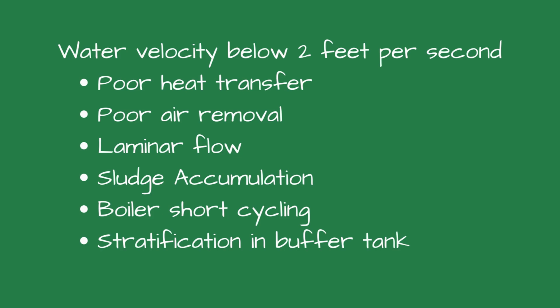At low velocities, small air bubbles tend to cling to the pipe walls instead of being swept along to the air separators. This leads to air pockets or air locking in terminal units, which reduces heating capacity and can cause gurgling noises. Poor air removal increases the risk of corrosion in the system. Flow may become laminar, smooth layered flow, rather than turbulent. Turbulent flow increases mixing and heat exchange, while laminar flow reduces system effectiveness, especially in heat exchangers and coils.